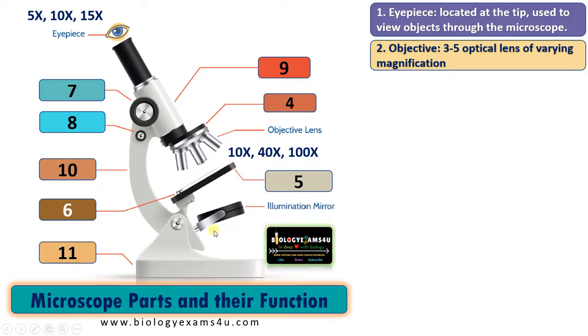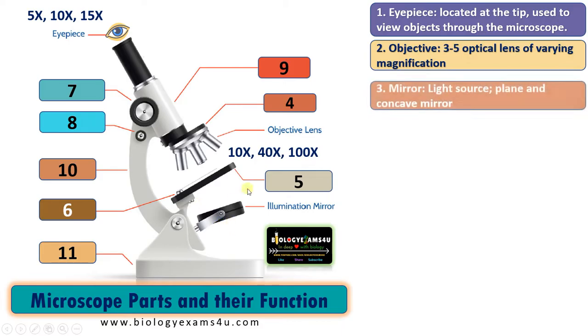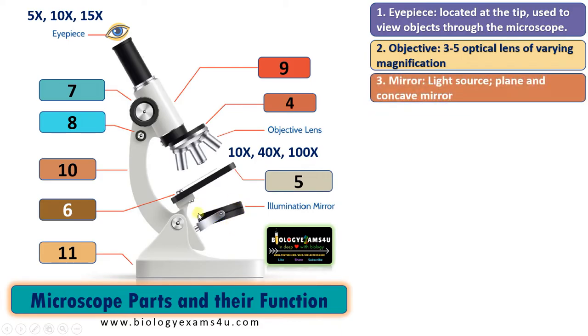The third part is the illumination mirror. This mirror has two sides: a plane mirror and a concave mirror. The plane mirror is commonly used when the light source is far away from the microscope, like daylight. The concave mirror is used when there is artificial light that is very near to the microscope — in that case, illumination will be better with the concave mirror. There is also a diaphragm just below the stage that controls the amount of light that reaches the specimen.